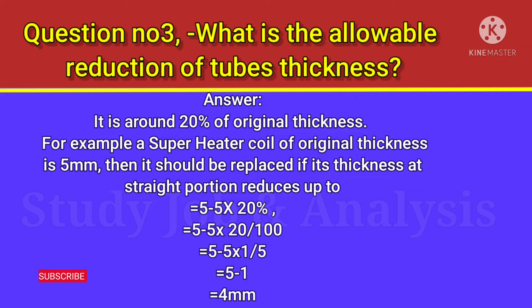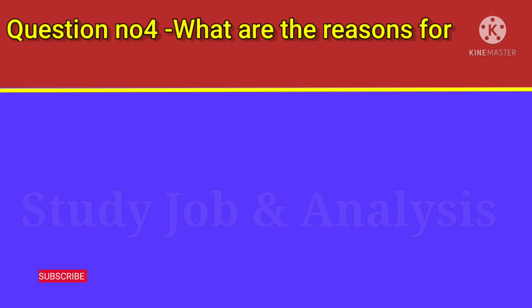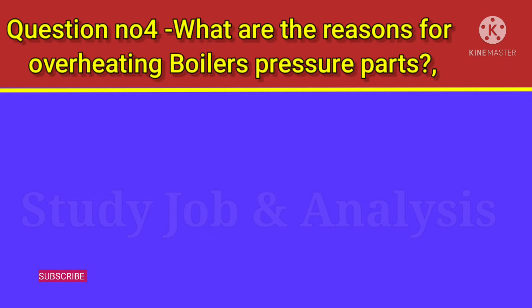For example, a superheater coil with an original thickness of 5 millimeters should be replaced if its thickness at the straight portion reduces to 5 minus 20 percent of 5 (i.e., 4 mm). Question number four: what are the reasons for overheating of boiler pressure parts?